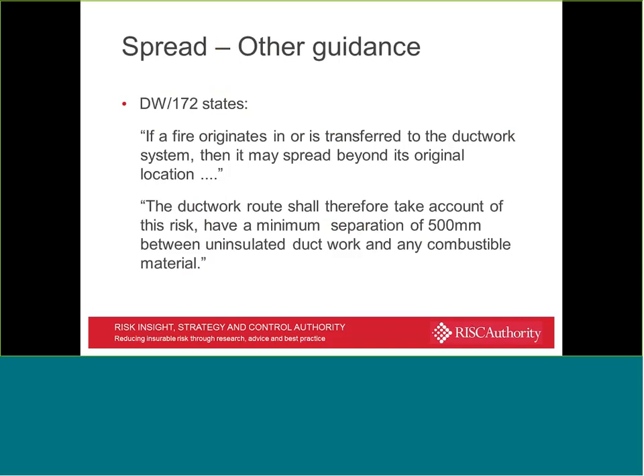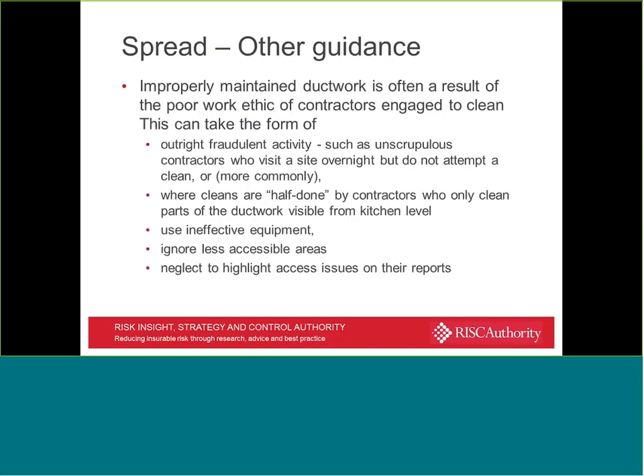There is guidance in approved documents to the Building Regulations, approved document J, I think it is, and within approved document B, it talks about service penetrations through combustible construction elements. But DW172 simply states a figure, a minimum separation distance of 500 millimetres. The reason being, if you've got a fire within the flue itself, then the ductwork is going to get extremely hot and maybe hot enough to cause ignition of materials located adjacent.